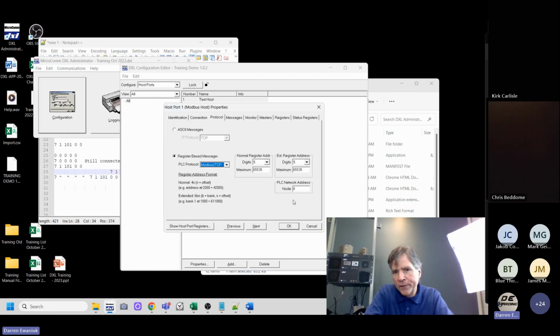With Modbus and Omron, all of the values within the PLC are given a register number. That's the particular data portion that you're going to read or write from. In the case of Modbus, the registers are typically numbered as either the block of registers from 40,000 to 49,999, which would be your integer values you can read and write to the PLC.